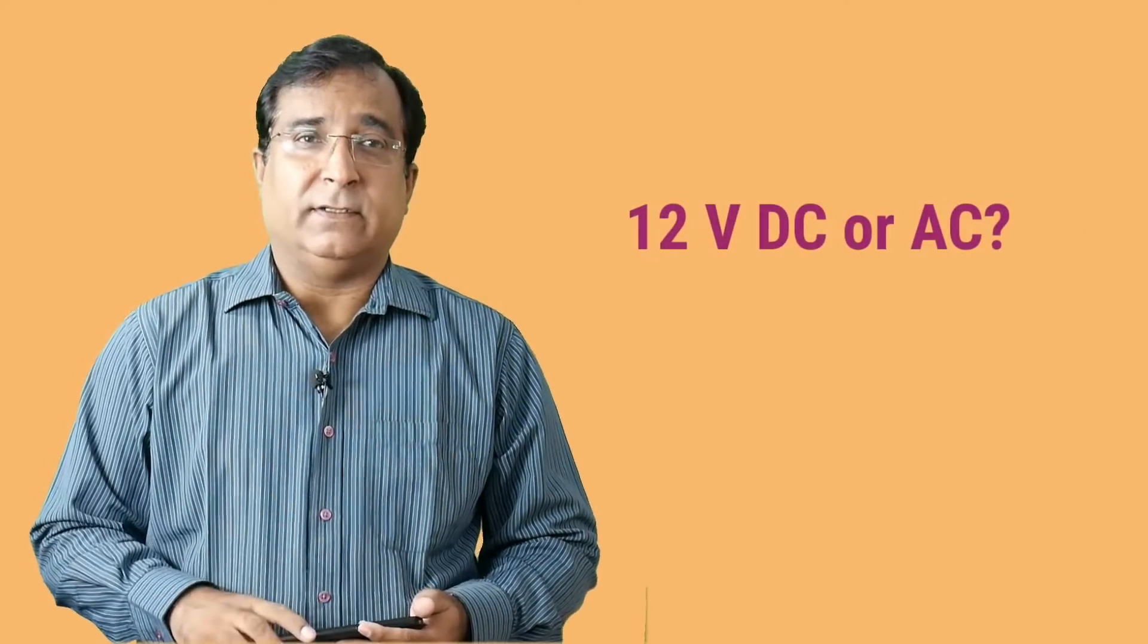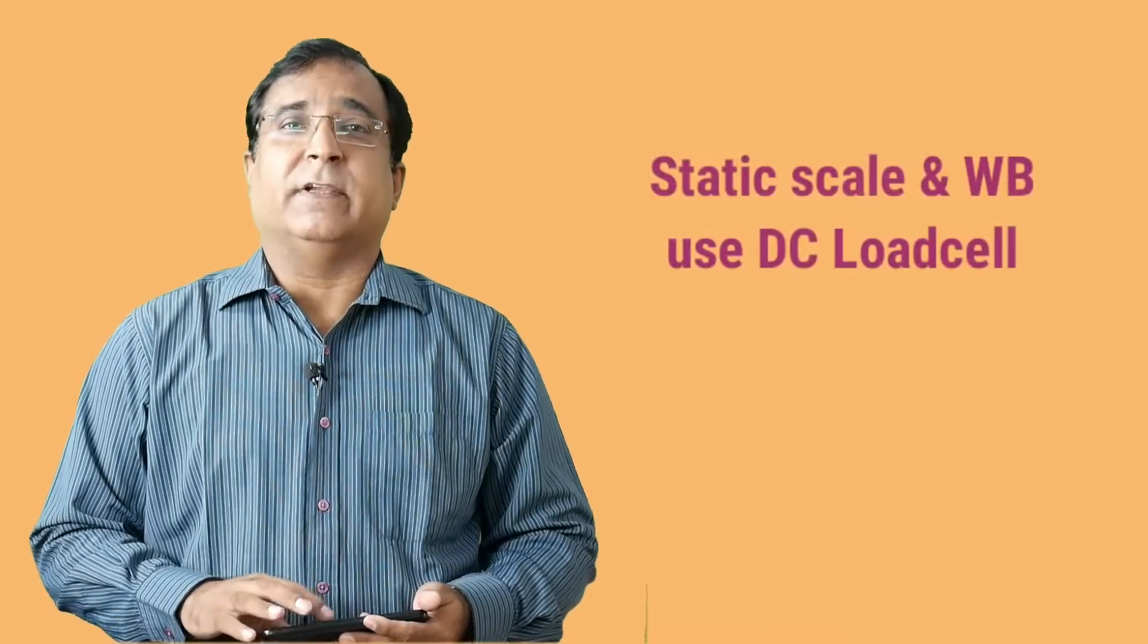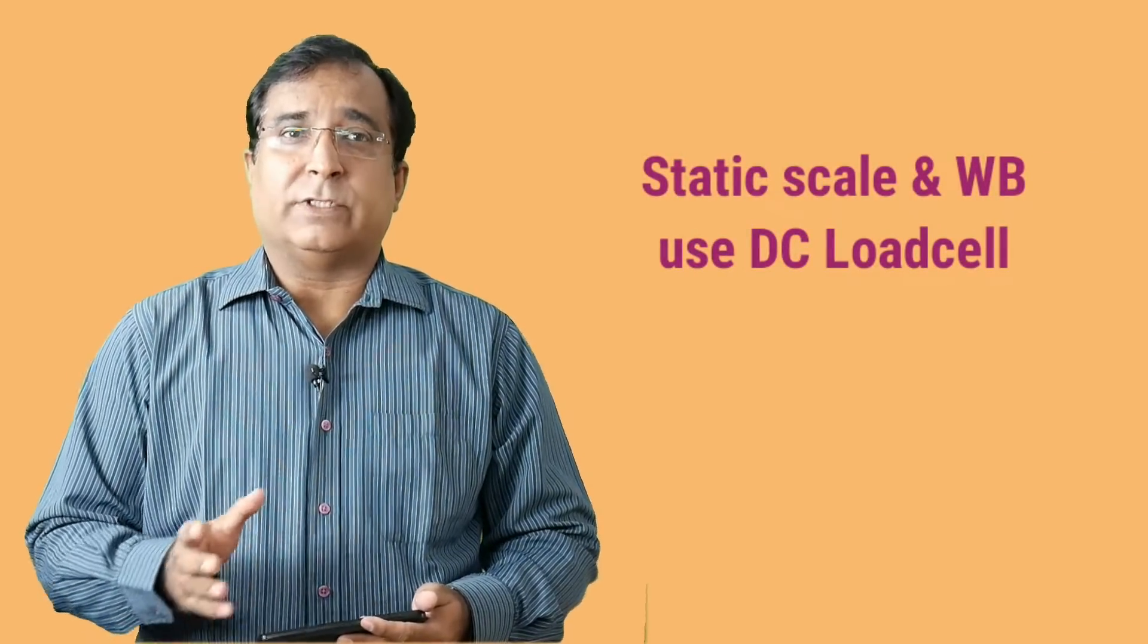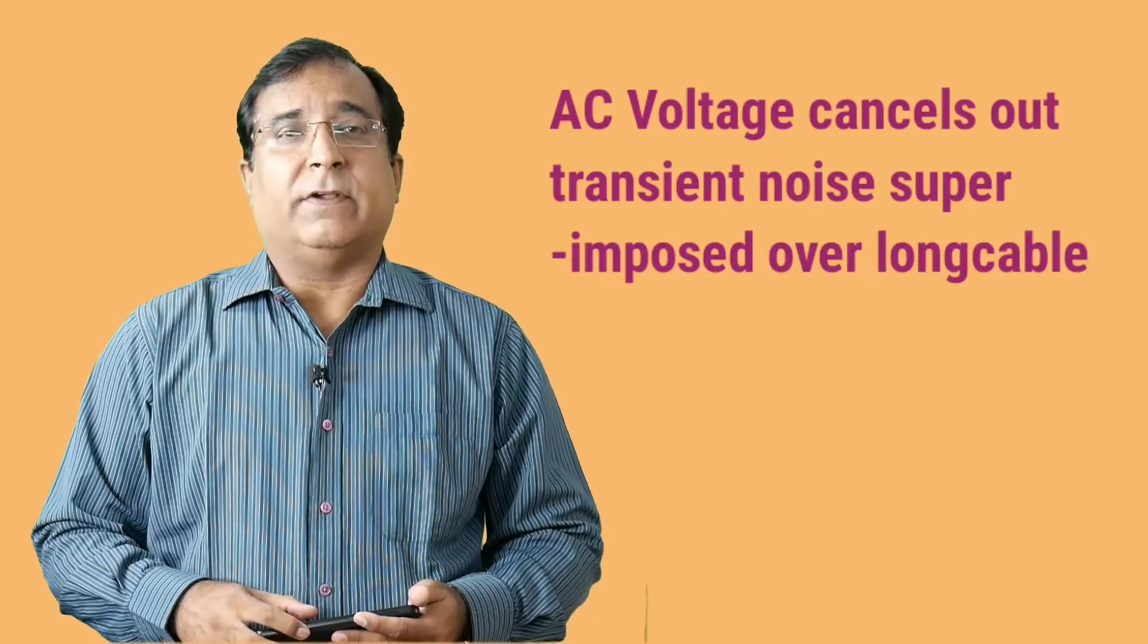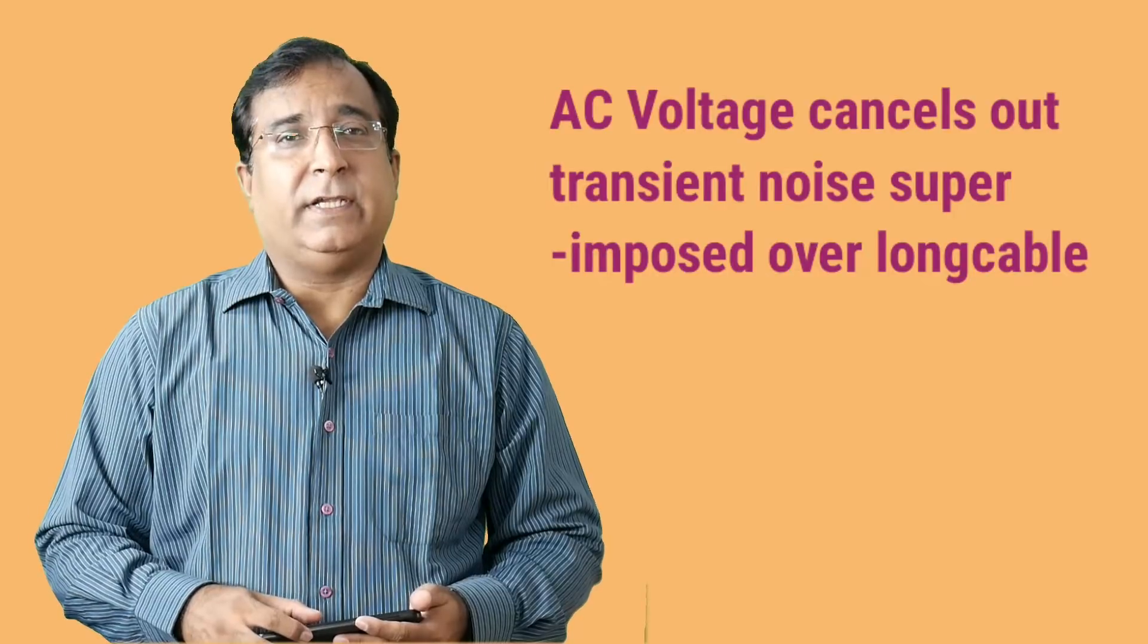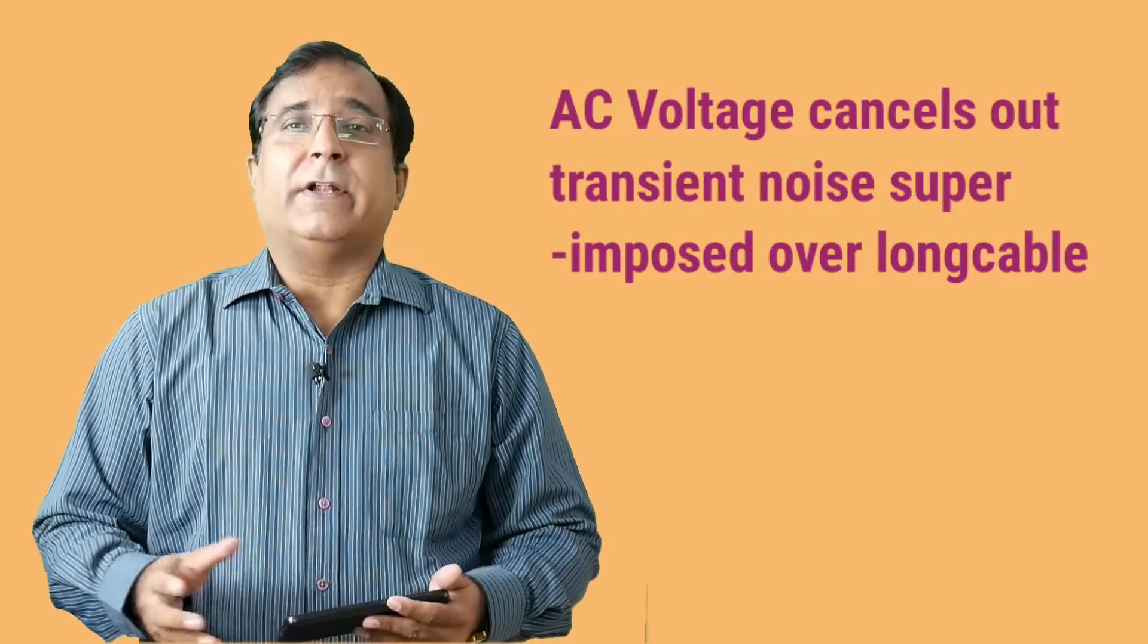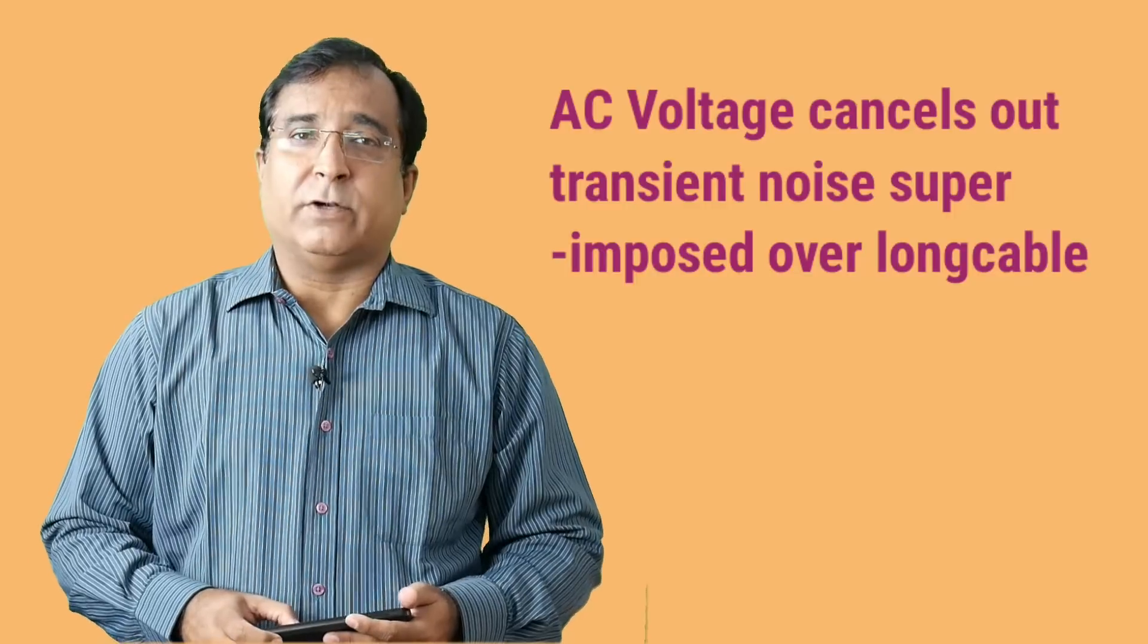Now this excitation is 12 volt AC or DC. Mostly this is DC voltage in static measurement such as weigh bridge, weighing scale where indicator and load cell is mounted in close proximity. But dynamic measurement system such as weigh feeder, belt weigher, solid flow feeder, it may have a high frequency AC voltage just to avoid induced voltage and noise superimposed over long cable running in plant operation.